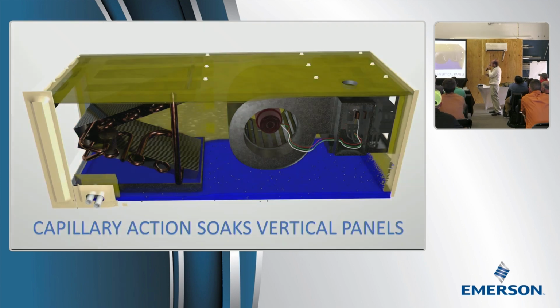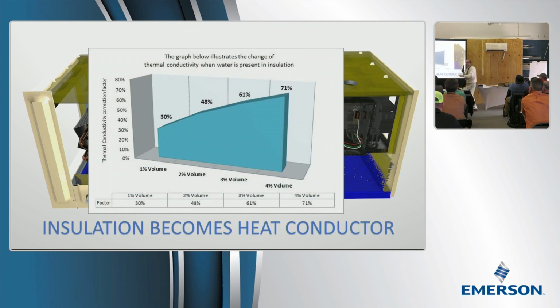Now, the other thing that happens is you do get this capillary action, obviously, where you'll start pulling water up the sides of it. Even if it began in the bottom, it'll start growing up the sides. Now, remember this, however it got wet, which is usually going to be vapor that condensed. Once 2% of the air, because that's what insulation is, little compartments of air, once 2% of that is water, you've just lost half the R value. You just lost half the R value at 2% wetness. If you get to 4% wetness, you're down to 30% of your R value.